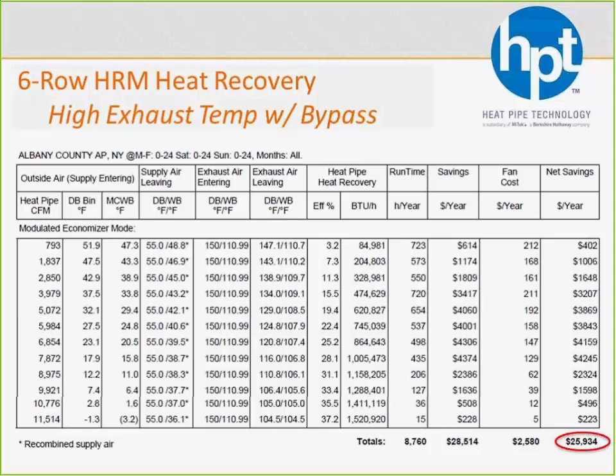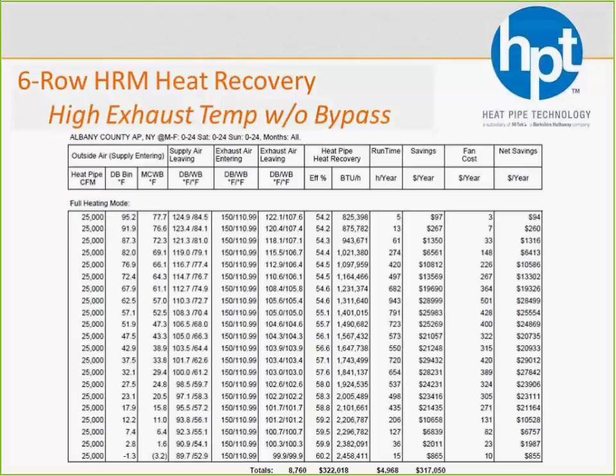So assuming that that's our cap, you'll see that for those bins where it's cooler than 55 degrees, we're going to save, at 75 cents a therm, even taking that static pressure hit of $2,500 you see below, just under $26,000 a year. That's going to give you, depending on how much the install is, probably between a 3 and 5 year payback for that setup. Now that's if we capped it at 55 degrees.